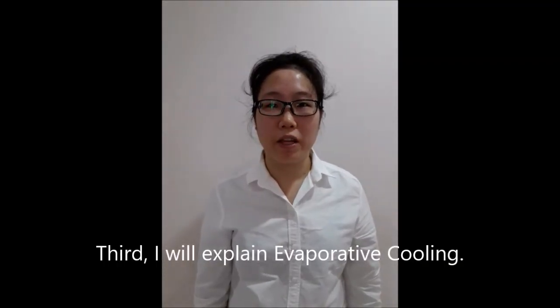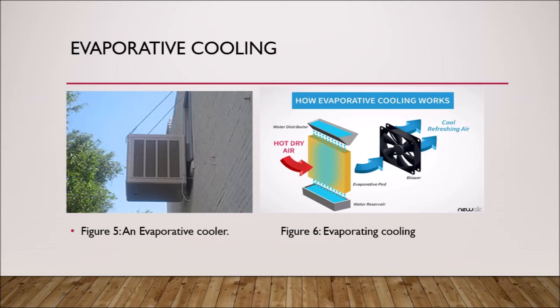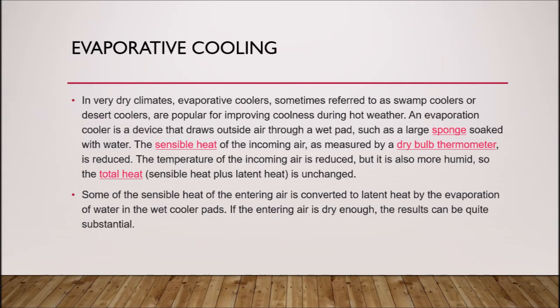Third, I will explain evaporative cooling. In very dry climates, evaporative coolers, sometimes referred to as swamp coolers or desert coolers, are popular for improving coolness during hot weather. An evaporative cooler is a device that draws outside air through a wet pad, such as a large sponge soaked with water. The sensible heat of the incoming air, as measured by a dry bulb thermometer, is reduced. The temperature of the incoming air is reduced, but it is also more humid, so the total heat, sensible heat plus latent heat, is unchanged.